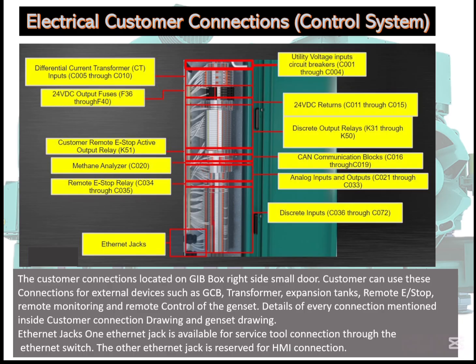In these relays, these are the outputs: common warning, shutdown, DCB closed, DCB open, utility DCB closed, utility DCB open, genset running. All of those are available on these output relays. Then we have a remote e-stop. If we want to connect remote operation parameters, there are connections available labeled with K51.